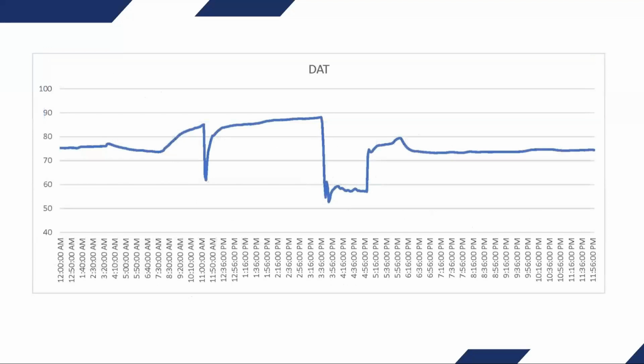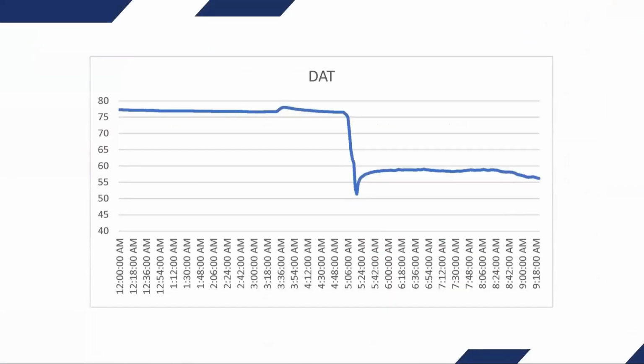This is just an example of the trend data that we were looking at on one of the makeup air units, one of the dedicated outside air units. You can see it was all over the place. It rarely ran in that 55-degree temperature range. Again, this one was supposed to deliver 55-degree air to the rooms, and it never did. I have another trend here that shows this is after we had all the corrections done. We were able to achieve that 55 or close to that 55.